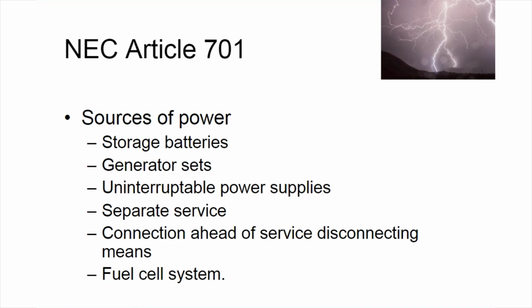Article 701 covers legally required standby systems. These are typically less critical loads than covered by Article 700. An example might be building pressurization or smoke management as required by 101 for high rises, as we discussed earlier, and also required for large places of assembly.